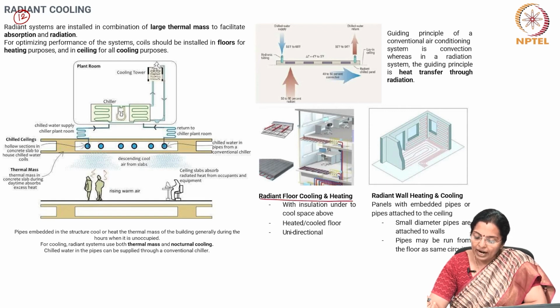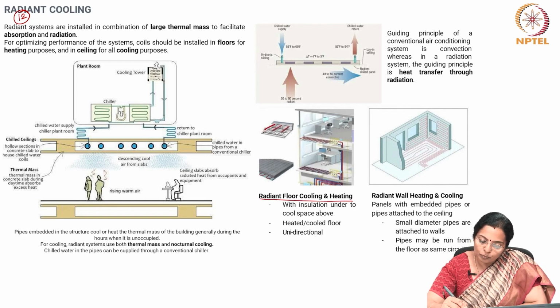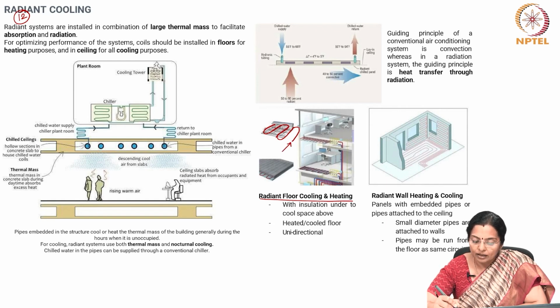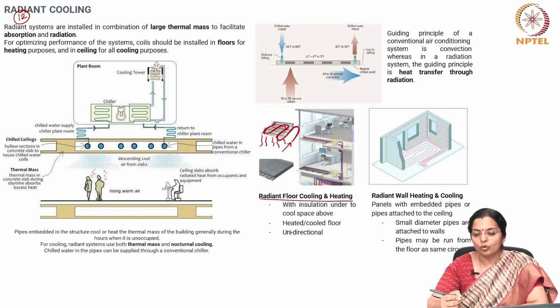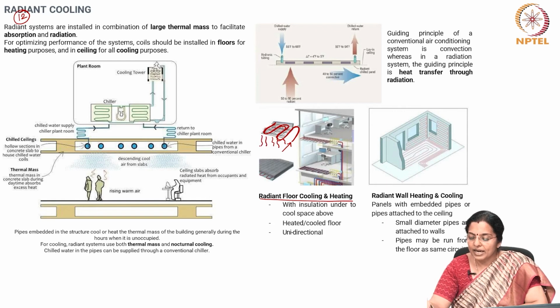Radiant floor cooling and heating has a system of pipes which runs across the roof in such a way that when the building needs to be cooled, cool water is sent into the tube, and through the process of conduction and radiation, it radiates the chillness into the room or absorbs the heat and makes the indoors cooler. When the indoors have to become warm, the water that is pumped inside must be warm water.